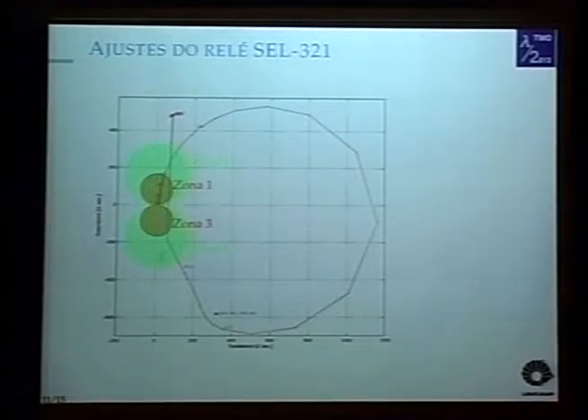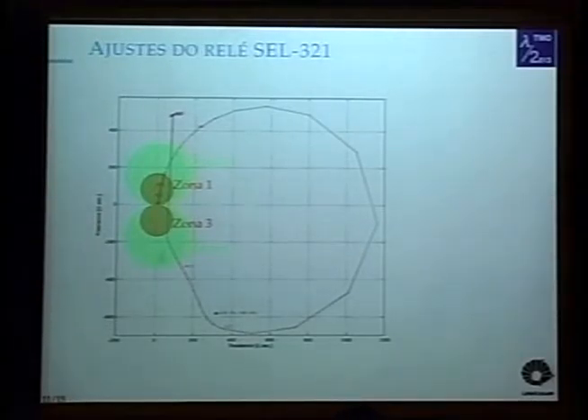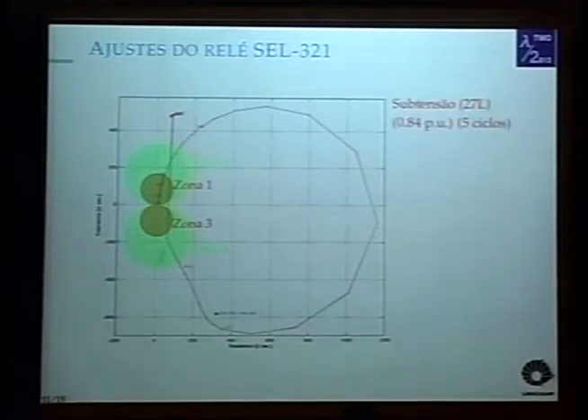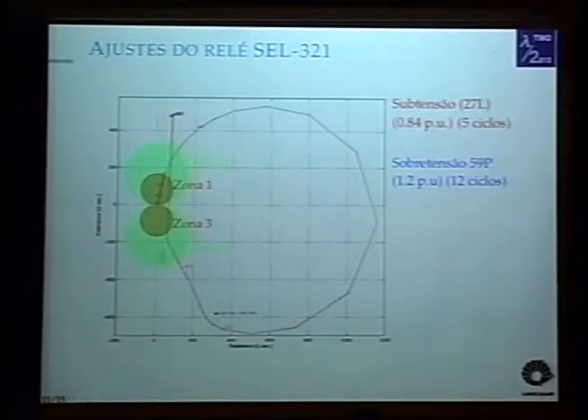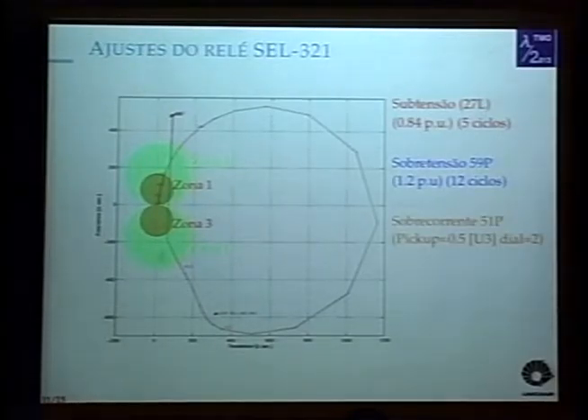So here, the relay shows in which zone the fault was found according to the adjustments we set up. If it shows zone 1, we have the information that it happened in this area of the line. If it shows zone 2, we have the information that the fault happened in this segment of the line. And with zones 3 and 4, that's why we used 4 zones, because we could have used only 2, one ahead and one reverse. We also used the concept of under voltage of 0.84 pu, over voltage devices of 1.2 pu, and the overcurrent relay with these adjustments.